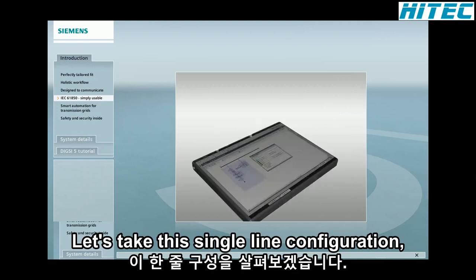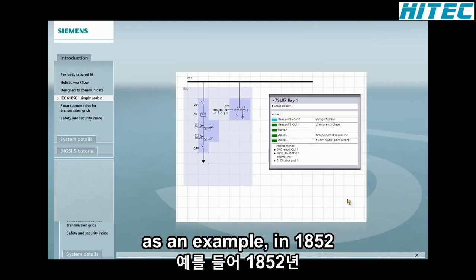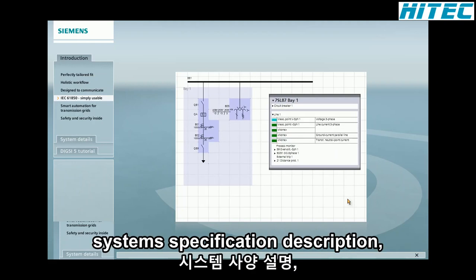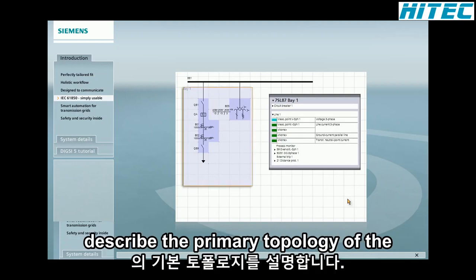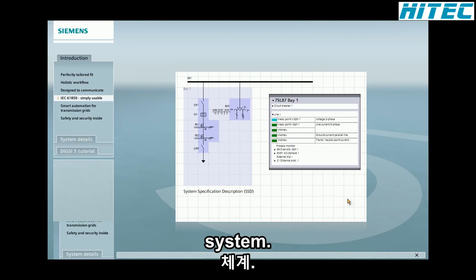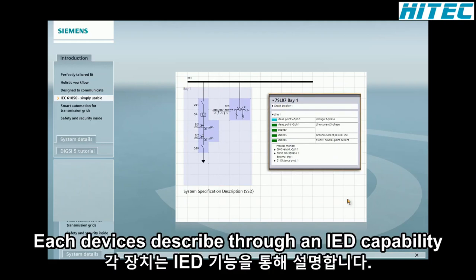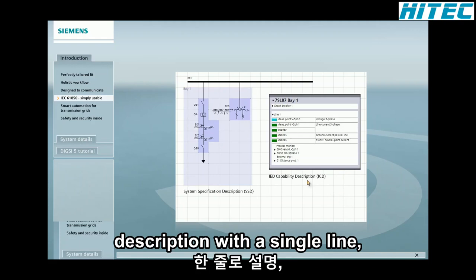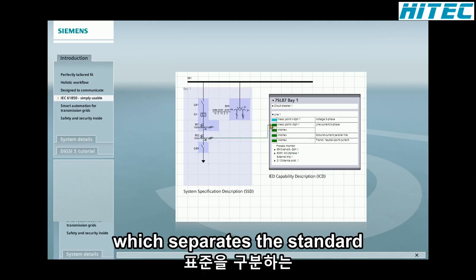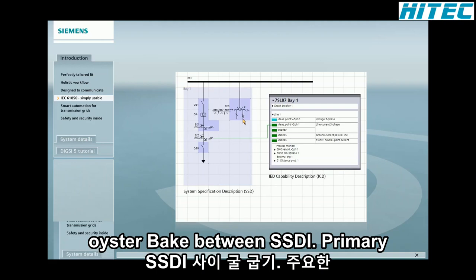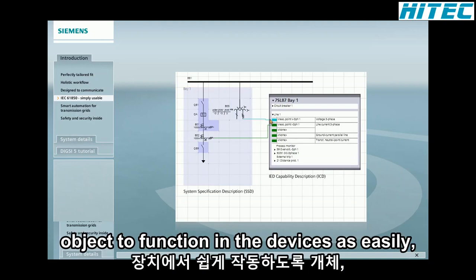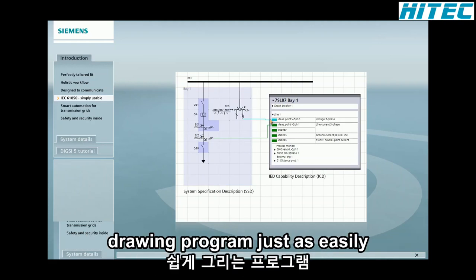Let's take the single-line configuration as an example. In IEC 61850, the system specification description describes the primary topology of the system. Each device is described through an IED capability description. With the single-line editor, you establish the standardized link between SSD and ICD by assigning primary objects in the bay to functions in the devices, as easily as in a drawing program.